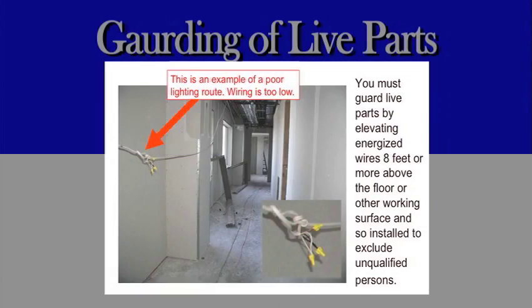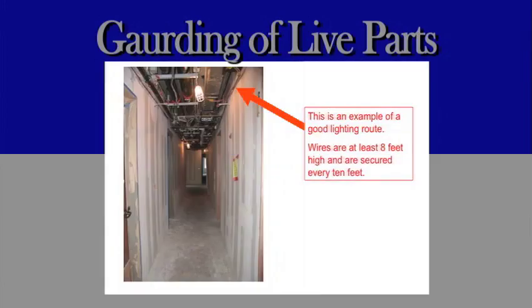This is an example of a poor lighting route. Wiring is too low. You must guard live parts by elevating energized wires 8 feet or more above the floor or other working surfaces and so installed to exclude unqualified persons. This is an example of a good lighting route. Wires are at least 8 feet high and are secured every 10 feet.